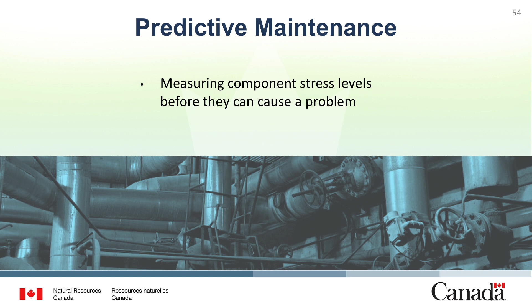In a predictive maintenance program, you would measure the component stress levels before they can cause a problem. You can measure component stresses through vibration, thermography, and oil analysis. You can measure the degradation mechanism and evaluate component performance through its power consumption.